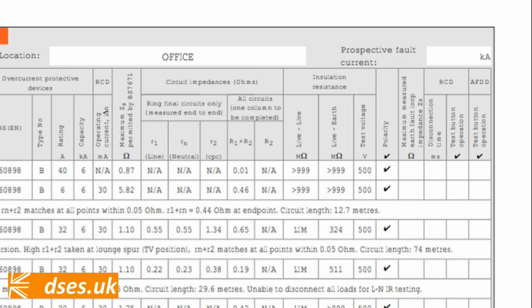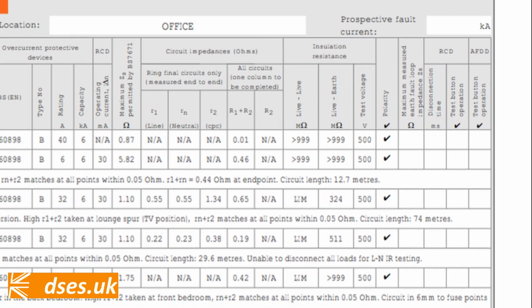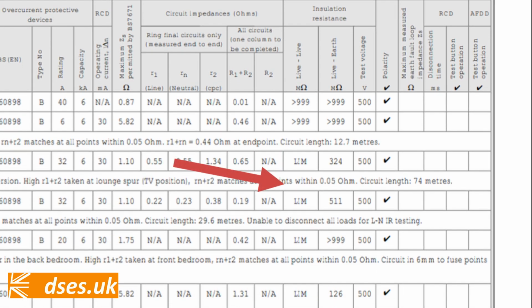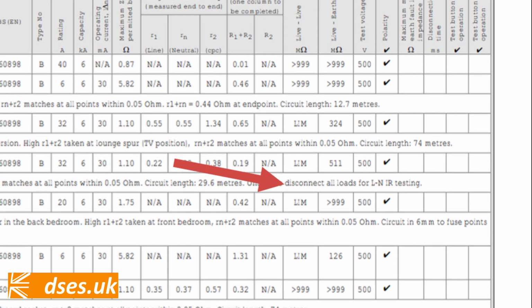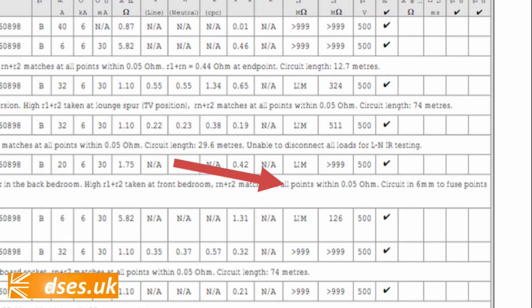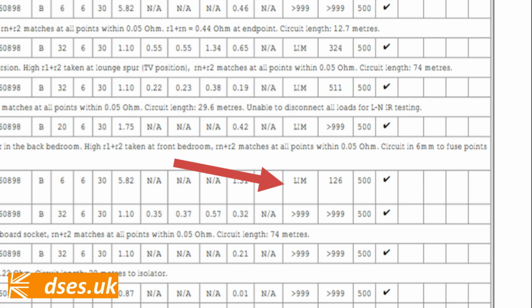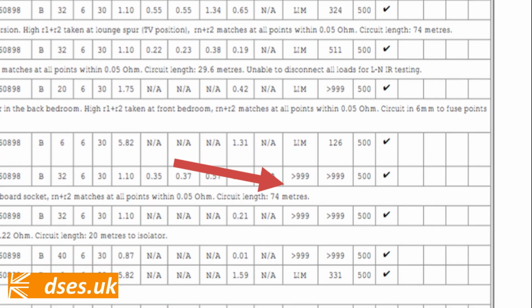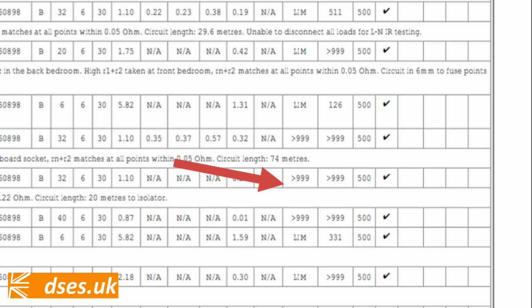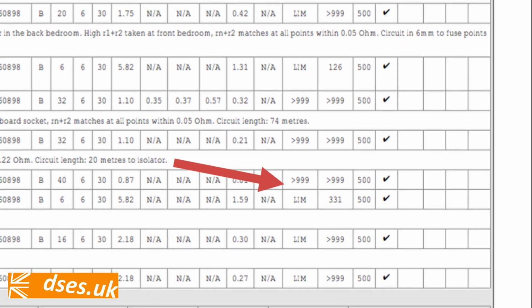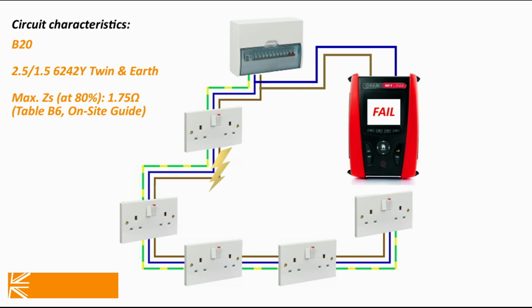As an example, the latest inspection I performed on my own home has line neutral IR testing limited for lighting and sockets. Those tests were undertaken in 2012 and they passed back then, but my installation is now more complicated than it was in those days, with USB sockets, bespoke RGB lighting, smart switching and all manner of permanently connected gizmos that I would have to wire out to prevent the test result from being skewed. As such, despite the fairly thorough inspection performed here and the data collated, there remains a risk of an existing parallel arc fault between line and neutral being present on those circuits whose testing has been limited.